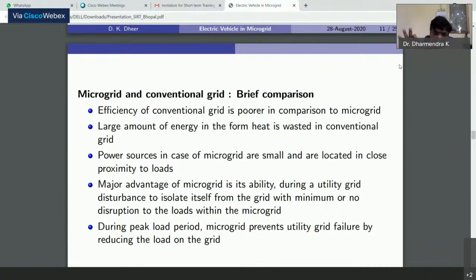And the major advantage of a microgrid is the ability, during a utility grid disturbance, to isolate itself from the grid with minimum or no disruption to the loads within the microgrid. So if it is connected to the grid and there is some problem in the grid, the microgrid can be isolated from the point of common coupling, and the loads within the microgrid can get power simply from the sources within that microgrid. That load and generation will be balanced. So without any disruption or with minimum disruption, power can be fed to that much load.